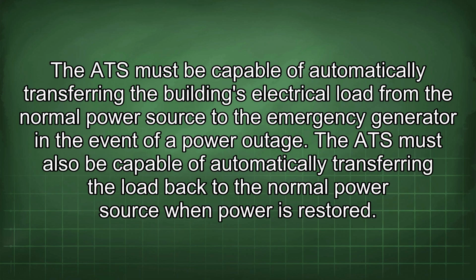The ATS must be capable of automatically transferring the building's electrical load from the normal power source to the emergency generator in the event of a power outage. The ATS must also be capable of automatically transferring the load back to the normal power source when power is restored.